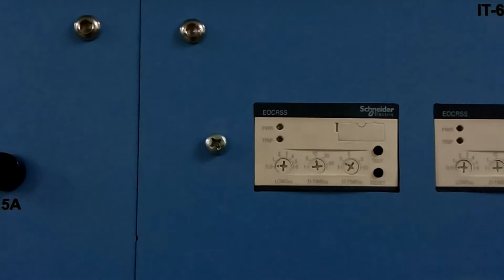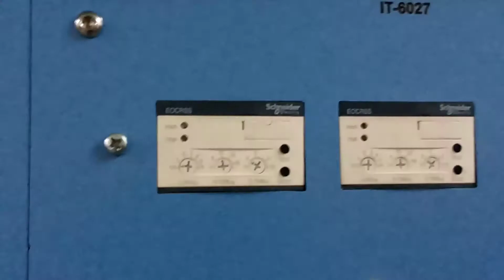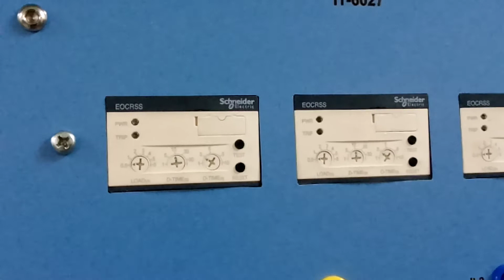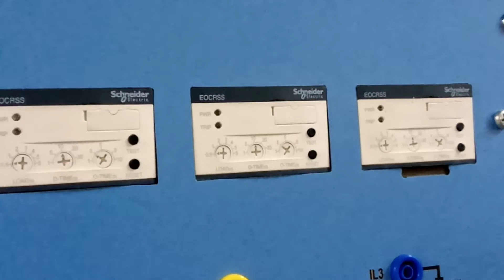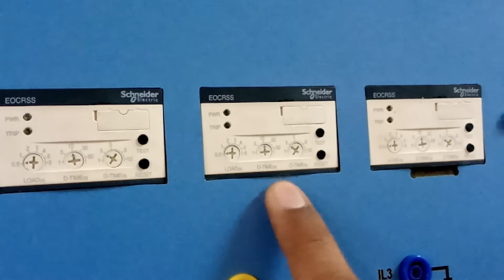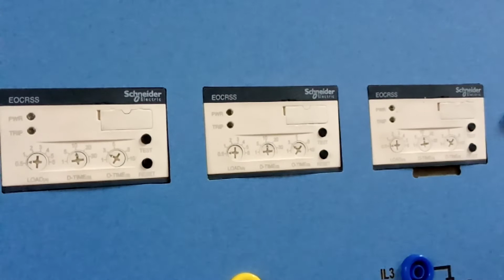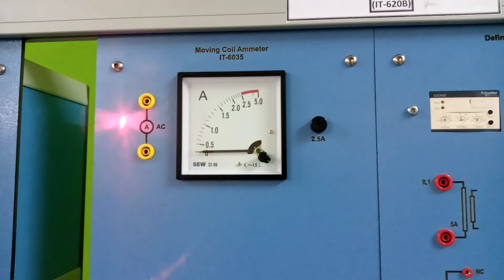So the D time is set on 10 seconds, and the O time is set on 3 seconds, and the load is on 0.5, and you can see that this is identical for all three. If I can show you all three here, you can see that this is identical. Like this is also 0.5, D time is 10, and operational time is 3 seconds, and same is for the third. So you have to be very careful, and you have to carefully calibrate all of these together. Next up we have an IT-6035 moving coil ammeter, and as you can see, this ammeter will be connected in series with your relay.